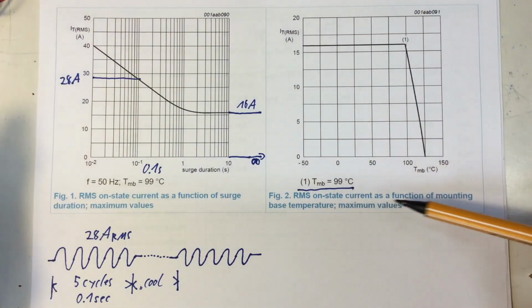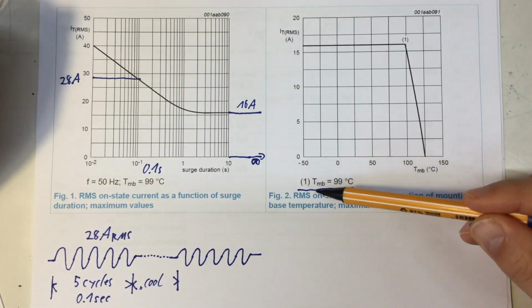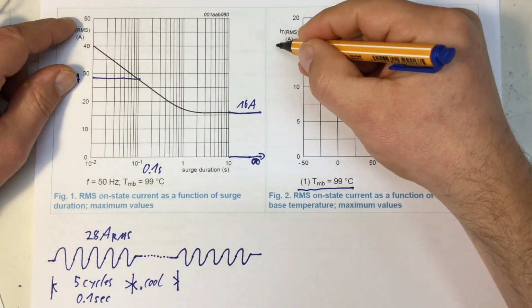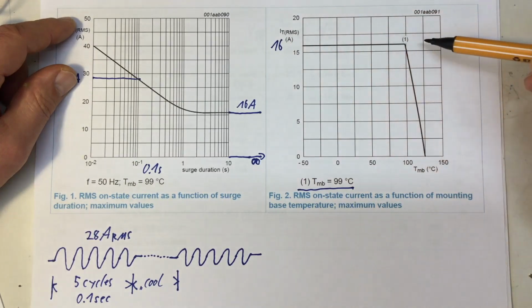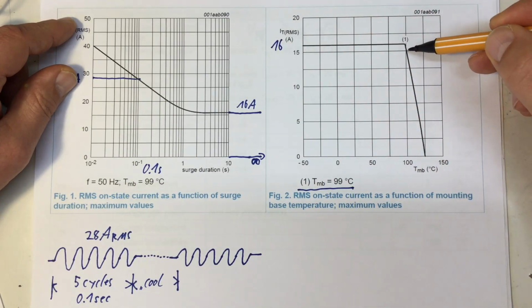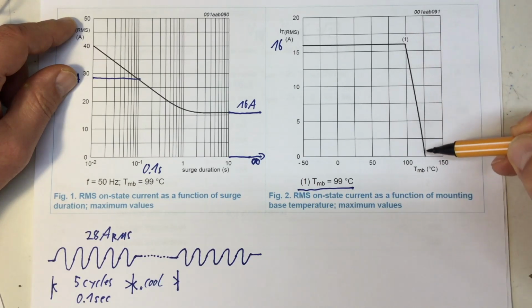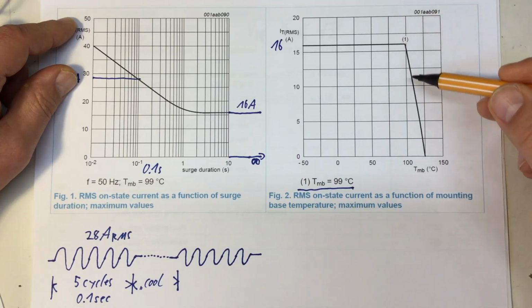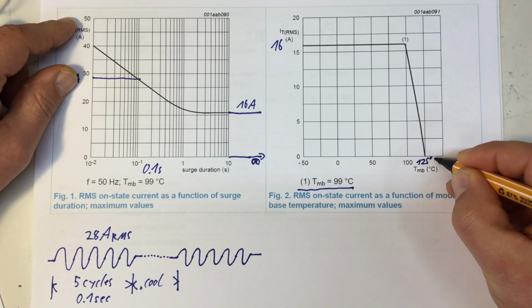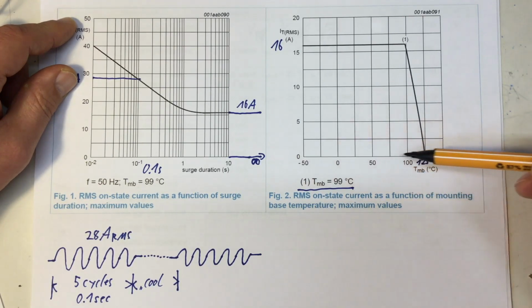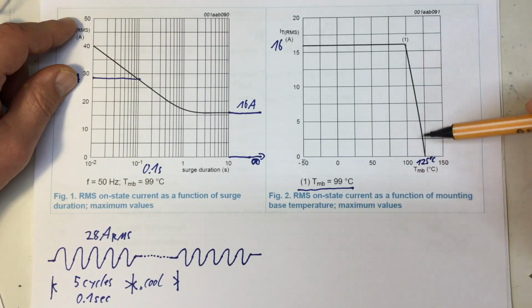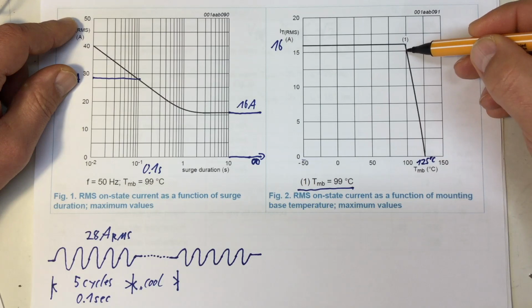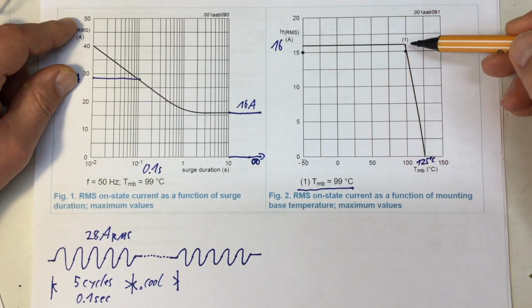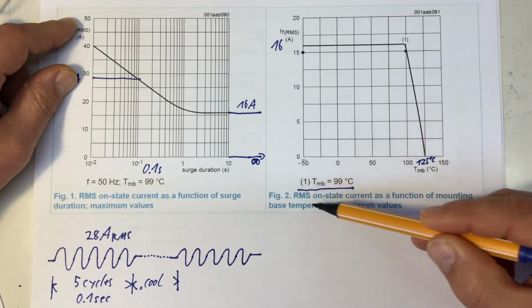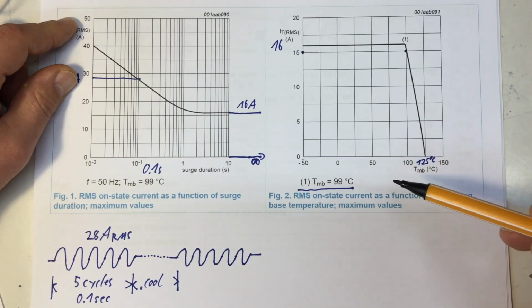The second figure is a little simpler to read. Remember, our mounting base has to be at 99 degrees C so we can pass 16 amps RMS current. Here you're shown how fast that rating degrades. As soon as you hit 125 degrees C on your mounting base, you cannot pass any current through it without destroying it. Even at 100 degrees Celsius we're down to 15 amps. So exceeding that mounting base temperature is a very, very bad idea.